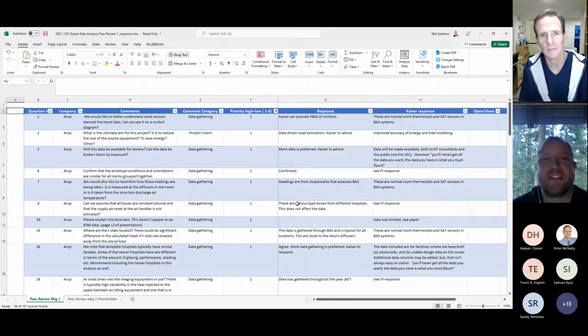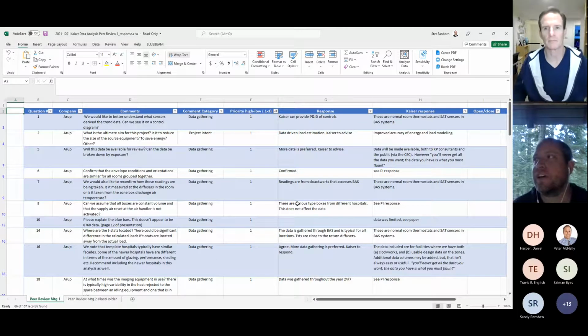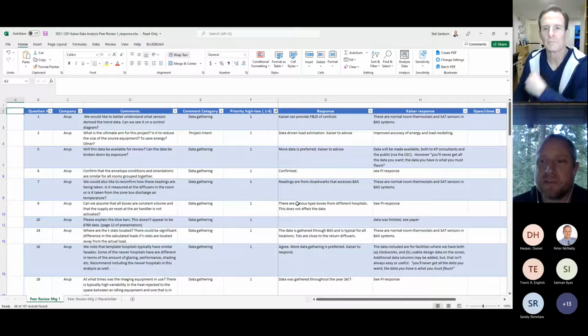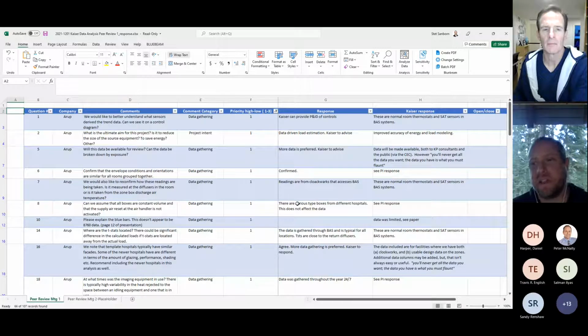Yeah, and I'll let Travis chime in for the ultimate goal, but what we really wanted to do is get a real life sense of, over the course of an entire year, what's the behavior of those spaces? How much variability do we actually see in the call for cooling? The actual cooling load in the space versus the 55-degree air that we're pumping and then reheating everywhere. Because even in VAV systems, there's a considerable amount of reheat, so what are the appropriate loads? And then ultimately, how does that correspond to the code minimum CFM that we have to pump through these spaces, and how often do we really need to design anything over code minimum CFM and meet load?